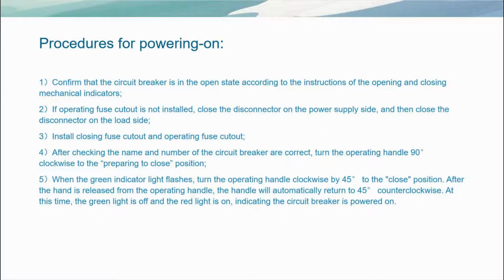Procedures for powering on. 1. Confirm that the circuit breaker is in the open state, according to the instructions of the opening and closing mechanical indicators. 2. If operating fuse cutout is not installed, close the disconnector on the power supply side, and then close the disconnector on the load side. 3. Install closing fuse cutout and operating fuse cutout.